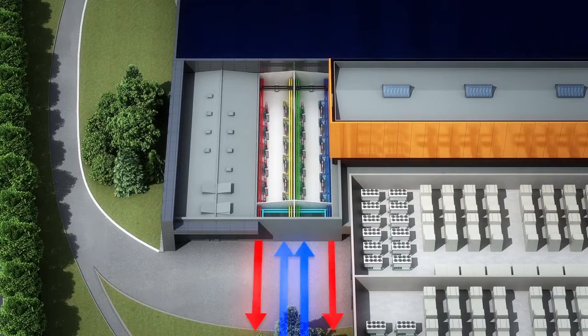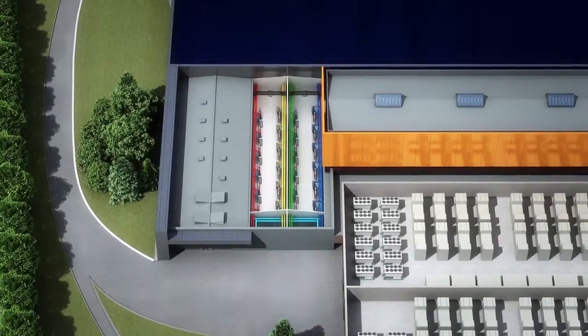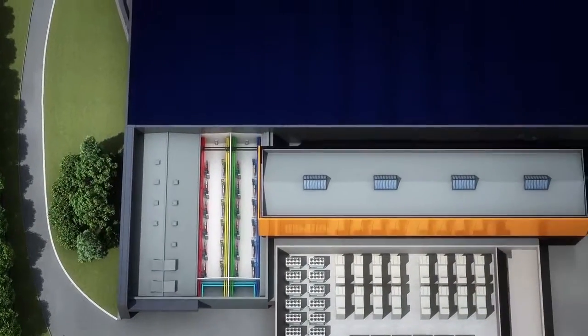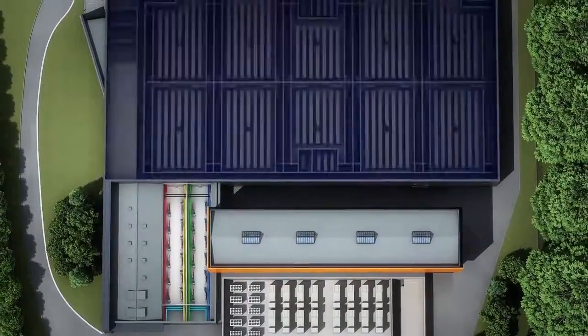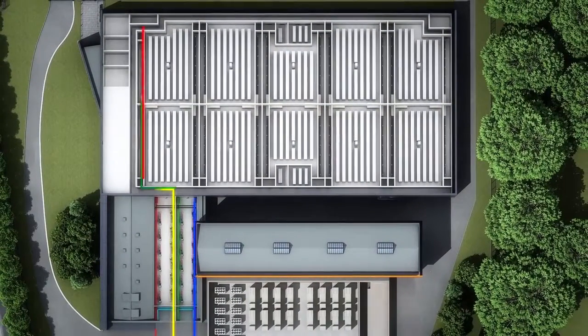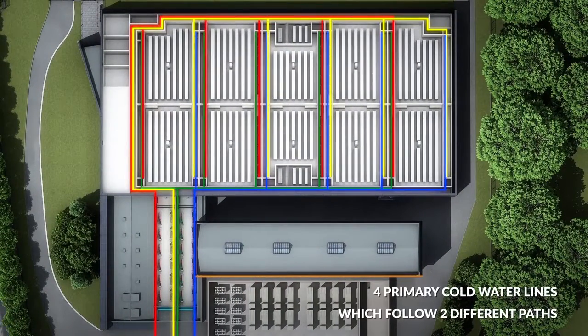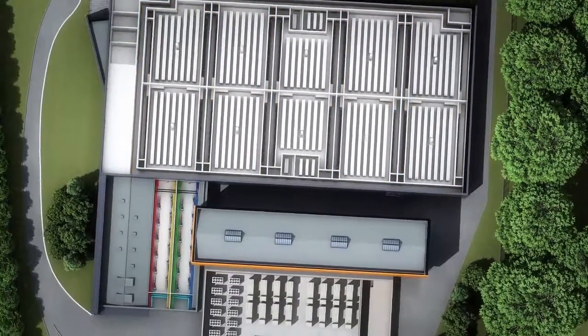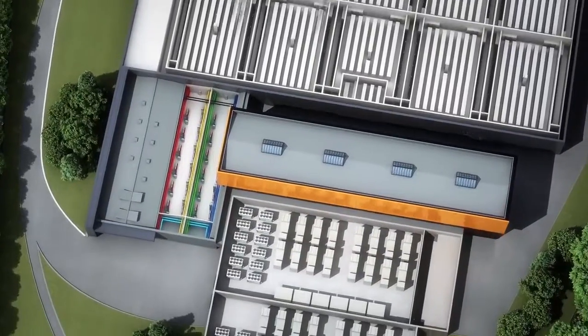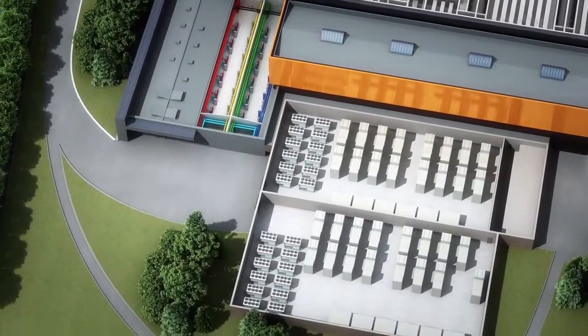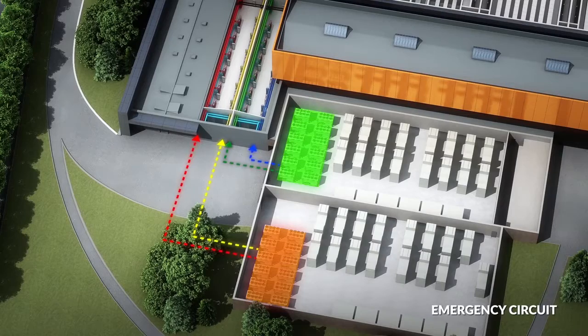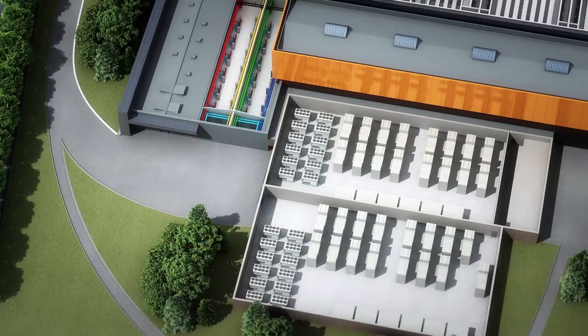After thermal exchange has taken place, the water is returned underground without any alteration in order to ensure that the hydrogeological balance is maintained. 4 hydraulic lines come from the exchangers, which follow 2 different paths to the data rooms. In an emergency, the air-water chillers located in the backup area come into operation and are able to provide 100% of the cooling power required in the data center.